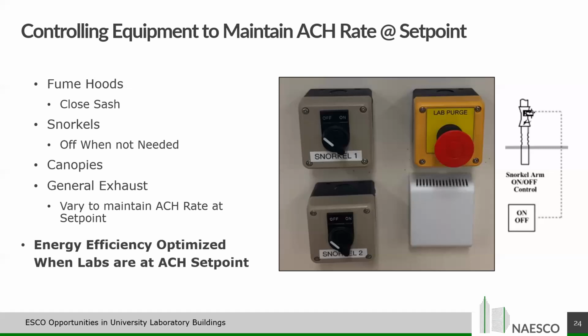In this particular case, we like to set up or install dampers in those snorkels and take some control of them. How we do that is by basically an on-off switch like you see on your screen, or by a timer switch as well, where we discuss with the lab users and put a timer switch for 20 minutes, 30 minutes, 40 minutes, an hour. And basically what'll happen is while they're running their experiment, they turn the snorkel on. And then after a predetermined amount of time, that damper will again close and basically provide savings for that end user. All this data will then get brought over to the room space controller, which will then calculate if the damper is open or not, and whether we need to keep supplying air or we can reduce that supply.